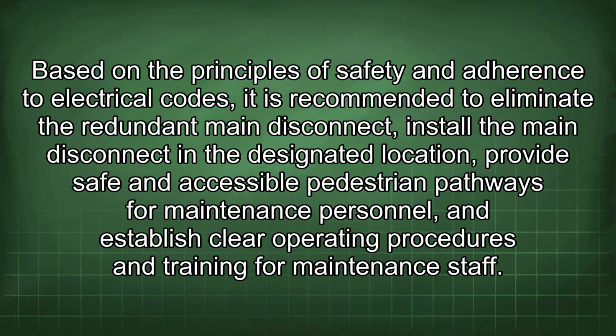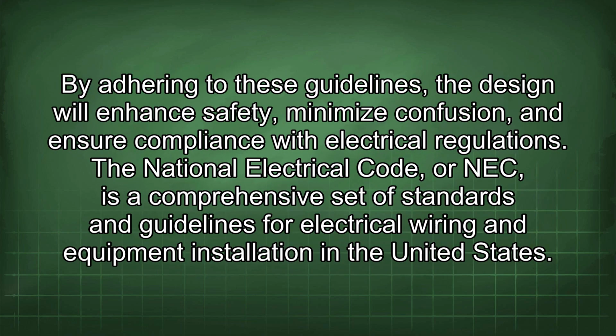Based on the principles of safety and adherence to electrical codes, it is recommended to eliminate the redundant main disconnect, install the main disconnect in the designated location, provide safe and accessible pedestrian pathways for maintenance personnel, and establish clear operating procedures and training for maintenance staff. By adhering to these guidelines, the design will enhance safety, minimize confusion, and ensure compliance with electrical regulations.